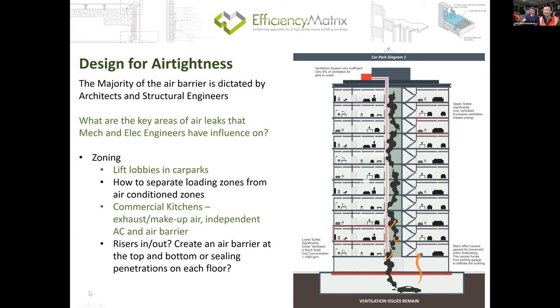Next thing, which is even more problematic, is commercial kitchens. You need to provide exhaust and makeup air, and to make matters worse, for the exhaust of a commercial kitchen you virtually can't put a damper in to control it after hours because of the grease and the potential for fire. Always try to consider what the alternative is to exclude that, or to make that an independent zone with its own air barrier and air conditioning.